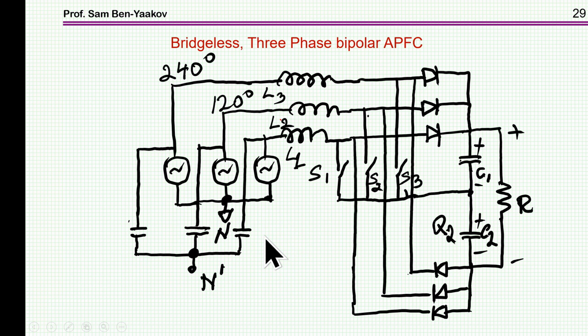For the control, we do need to sense the voltage referred to the neutral. If the neutral is not available, you can generate an artificial neutral point by having three capacitors summing up, which will act like a neutral point. You can measure the voltage across this capacitor, which also helps, and you may also have a high frequency filter here. This will be a cleaner waveform than just looking at the line itself. So here you have the reference neutral, an artificial neutral point, generated with the three capacitors.